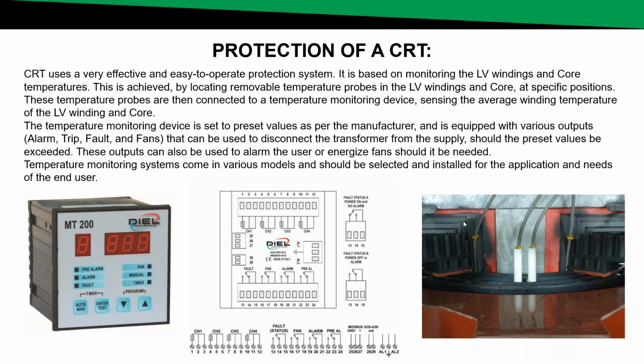specifications and construction of a cast resin transformer, let's look at some of the protection needed for cast resin transformers. So we all know the usual protection systems that are used for oil type transformers. They are sometimes very complicated and can give you nuisance tripping and lead to a lot of downtime and unnecessary power outages. Cast resin transformers use a very effective and easy to operate protection system. This protection system is based on monitoring the LV winding and core temperatures. This is done by locating a removable temperature probe in the LV winding and core at a specific position.